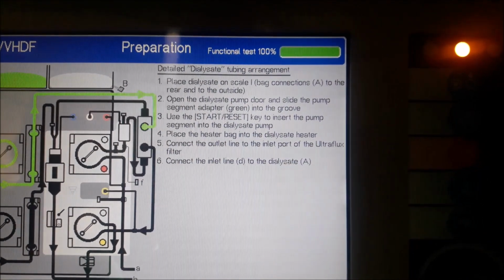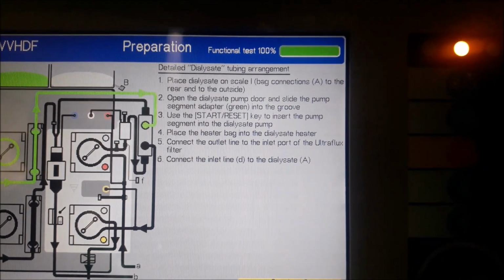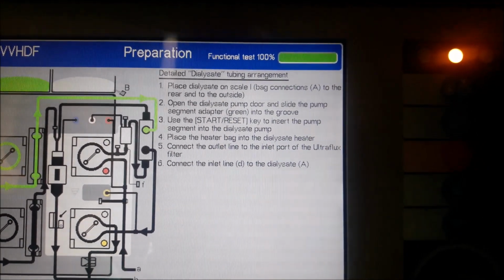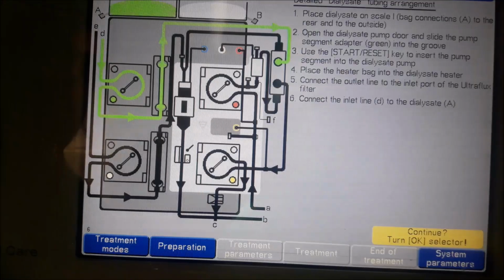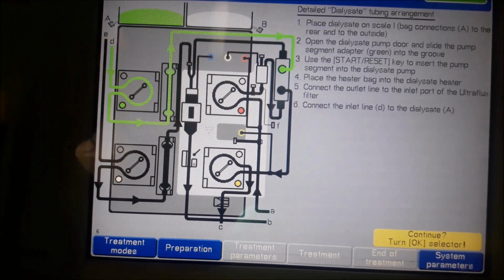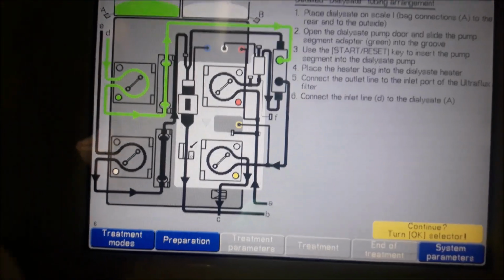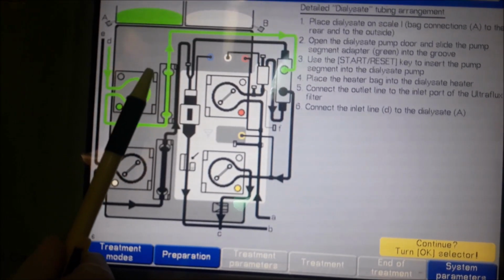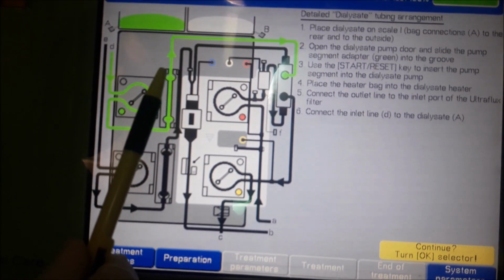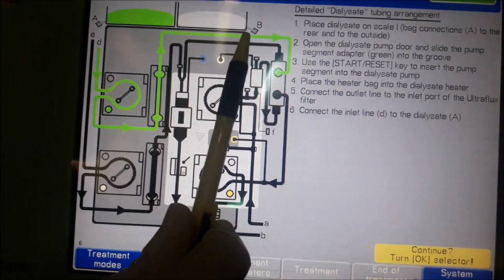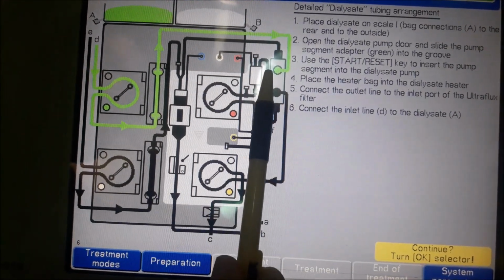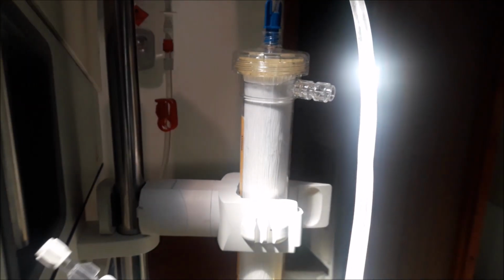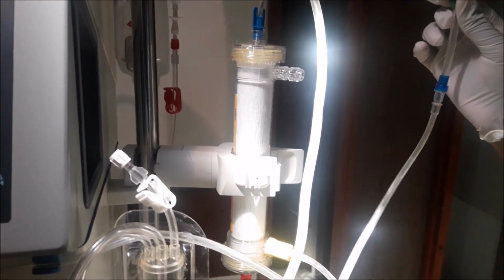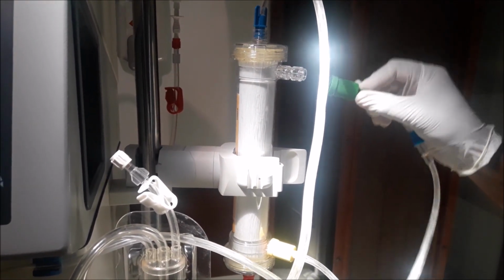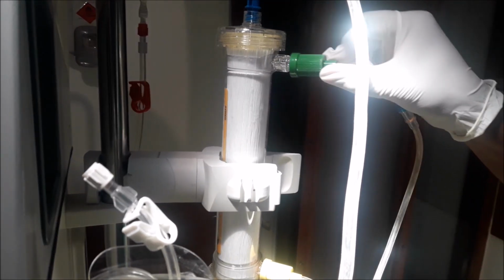Point number 5 is connect the outlet line to the inlet port of the Ultraflux filter. Let's review point number 5 in the image. The dialysate tubing is moving from the dialysate heater toward the Ultraflux filter. We already know this is our Ultraflux filter. Now we will attach our dialysate tubing to the Ultraflux port.